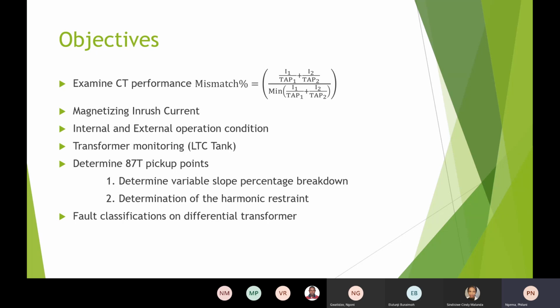As we know, the differential protection only has to respond to an internal fault condition, not an external one. It has to restrain when it's an external condition. So the determination of the pickup points, which is the pickup current, also has to be determined according to the dual slope, which is the slope that determines whether the relay has to restrain or the relay has to operate.